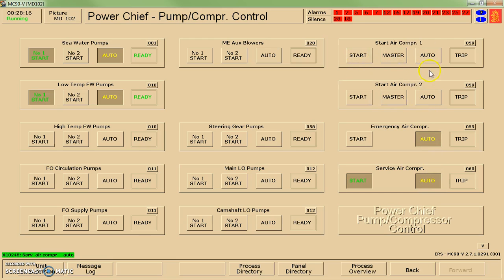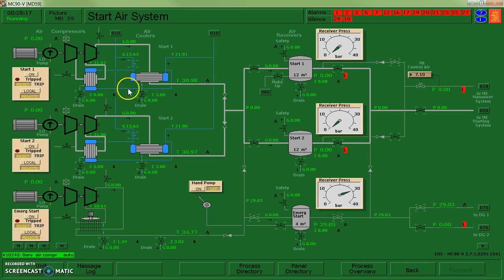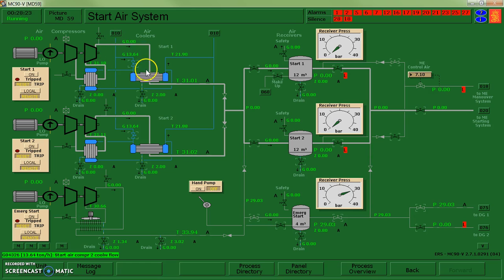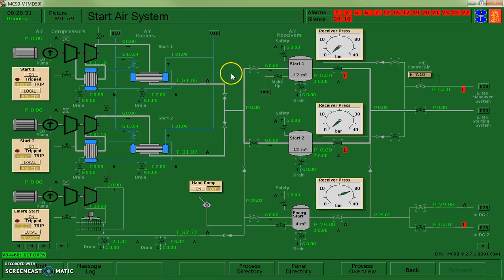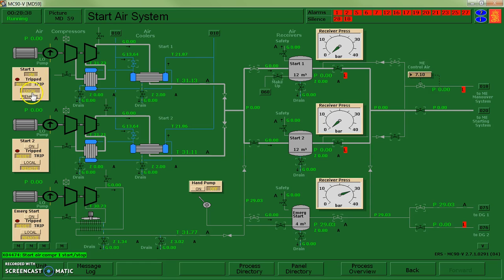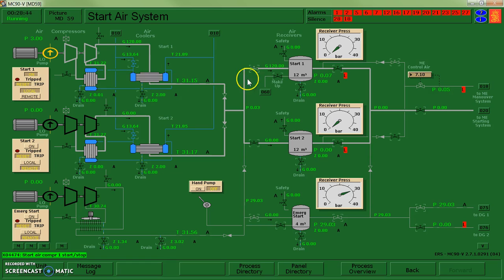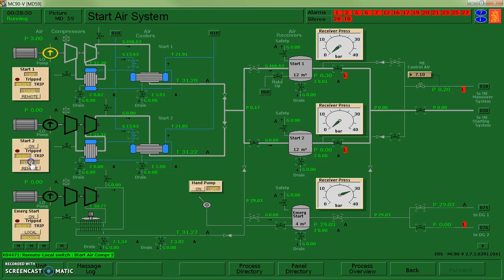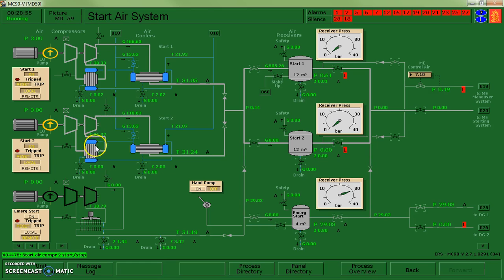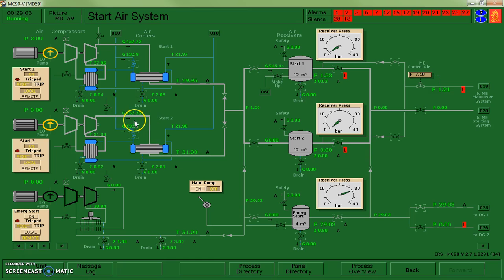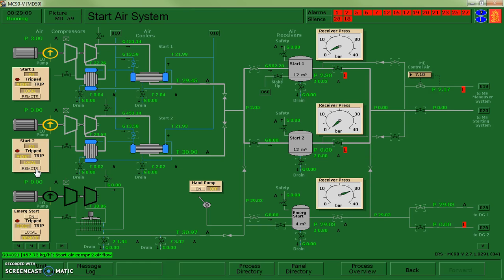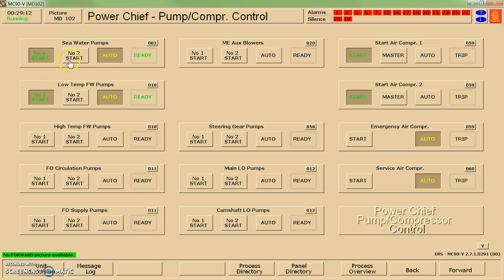I'll do the same with my start air compressors one and two. I've got cooling water to each of these, following through the pathway - dual stage, intercool, after cool. Let's start air one receiver and we'll start filling that guy up. Switch them to local to make sure he's running. It appears that my pressure is starting to rise in that tank. I'll do the same with this guy, make sure this guy's running as well. Appears that he is functioning. I'm happy with how they're working, so I'm going to switch them to remote and switch these guys into auto mode as well.